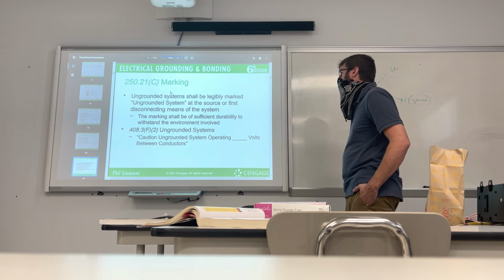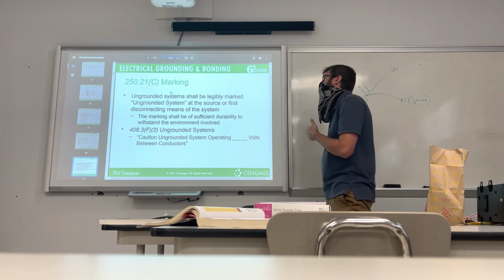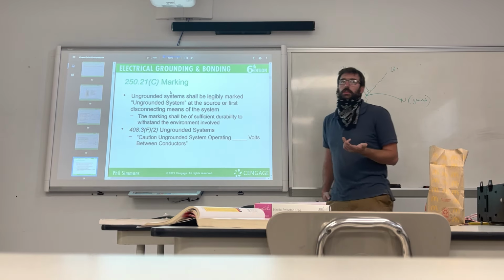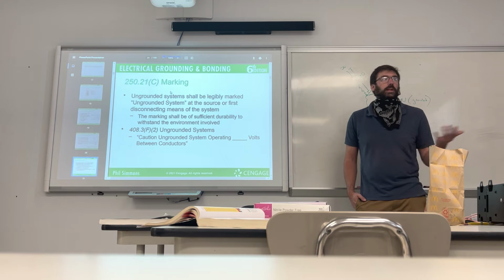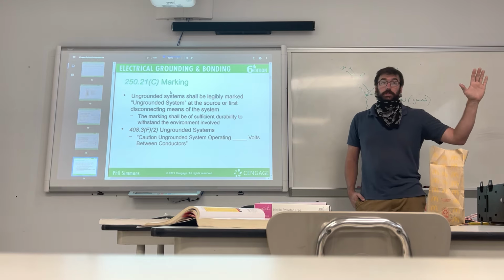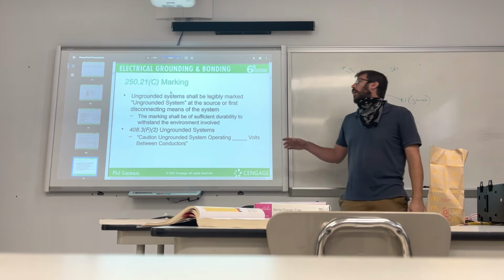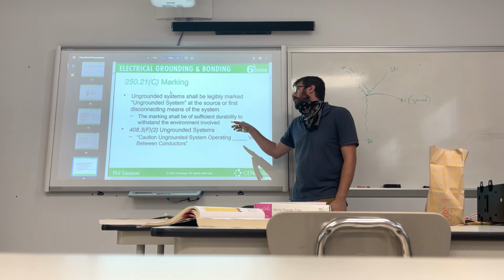408.3 F2, ungrounded systems. Caution, ungrounded system operating blank volts between conductors. All right, yeah, so that just makes sense, right? If there's a dangerous situation, you want to alert anybody walking in that building, hey, this could be potentially deadly, all right? I know they haven't talked about it much, but marking shall be of sufficient durability.